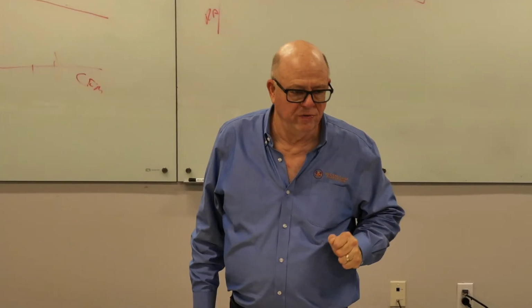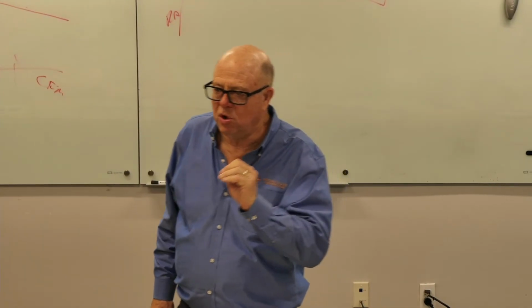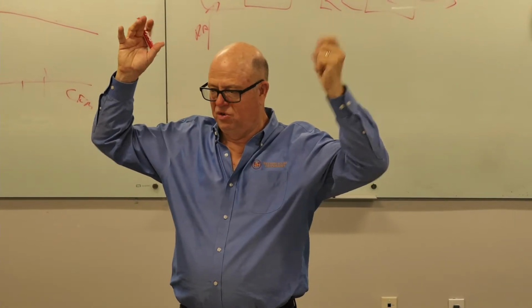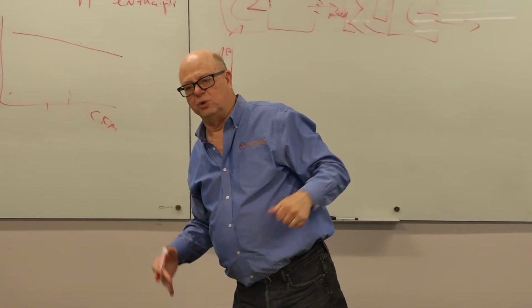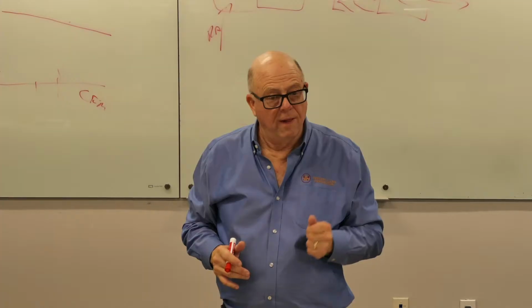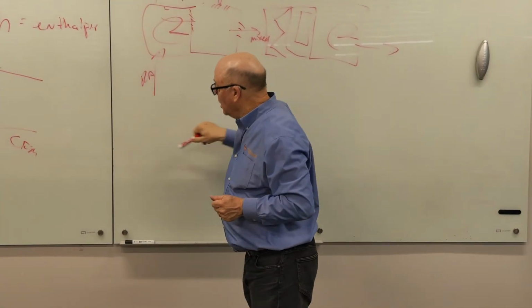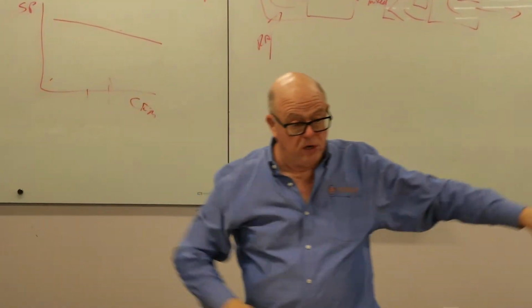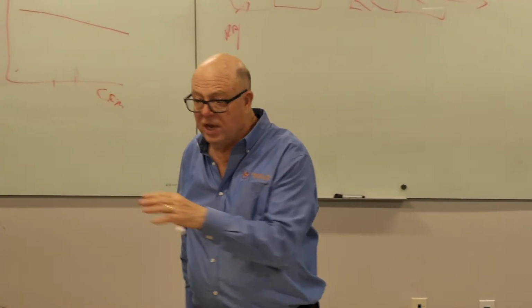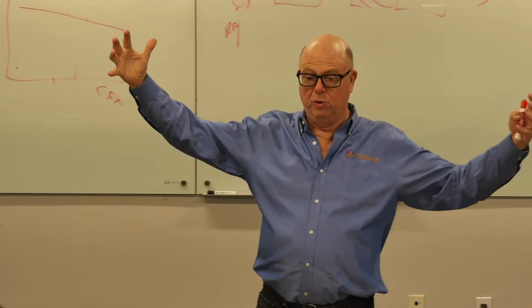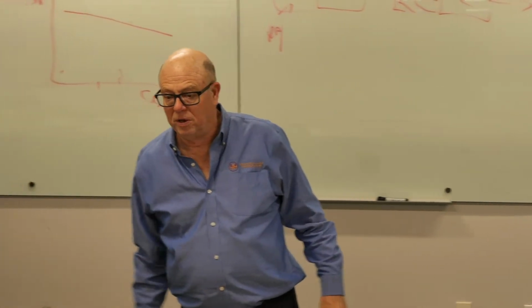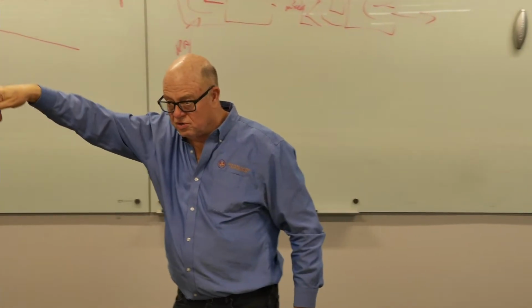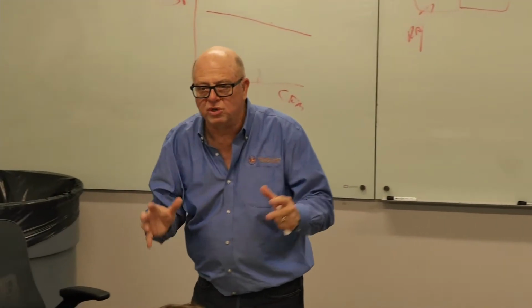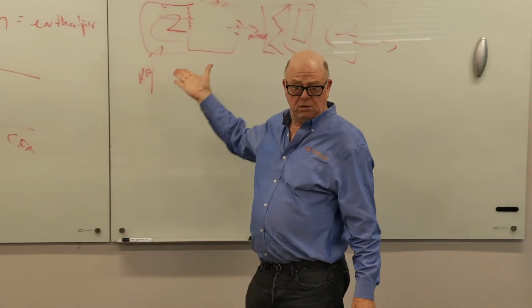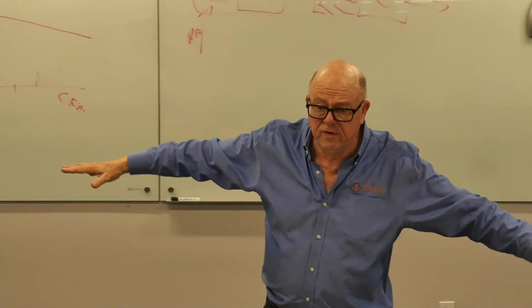Do hospitals use ducted returns? The short answer is yes, because they want no cross-contamination between rooms in some ceiling. So every space is, that's a little bit of an exaggeration, but it's more or less true. Every space is ducted return. What's your balancing act? You're pulling a lot of static pressure resistance, and that ducted return system from every room is going to have balancing dampers. Test and balance in a hospital, or test and balance with a real big return system, is twice the money as test and balance in the normal air conditioning application, because you have to balance the return as well as the supply, because you've got a certain amount of air that's supposed to be leaving every room. Okay? And so there's a lot more static pressure. And that is the legitimate reason to use a return fan, is you've got an extensive return duct system. Okay.